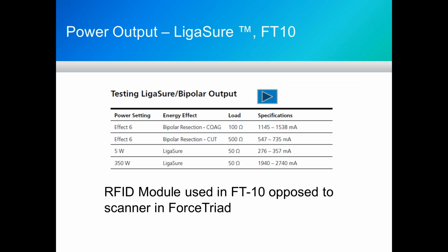So we're going to jump to LigaSure now. A couple of differences here as well as to what we can do for settings with LigaSure. You'll see this as we start to go in and show the video. But we used to set 3 current values. We'd start at 1 amp, we'd go up to 2.7 amps, and then we would go up to 5.5 amps. And of course, this would all be done in the triad. We actually call this debug mode rather than service mode, where we would set our current value.